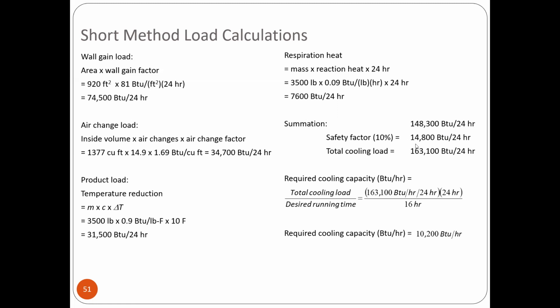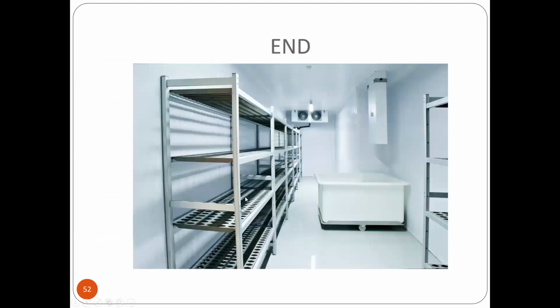Safety factor of 10% is 14,800. So, that gives a bit more, but it's okay, round up. Considering significant figures, the total cooling load is 163,100 BTU per 24 hours. Now, the required cooling capacity for 16 hours is 163,100 times 24 over 16, which is 10,200 BTU per hour. This is the cooling load for short storage.